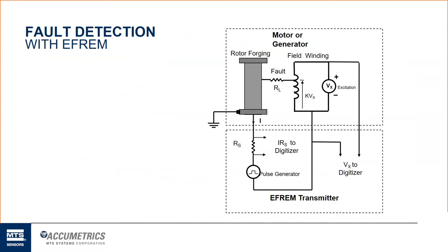So here's a little bit of an example. What's different with the EFREM system versus the classical method is that instead of injecting just a set DC voltage, we inject a pulse that's toggled from high to low. We also connect to the positive side of the excitation field and the negative side. As that pulse is toggled from high to low, we're doing two simultaneous high speed digital computations of the resistance value between the negative side of the field and rotor ground, and the positive side of the field and rotor ground, and transmitting that off of the shaft simultaneously.